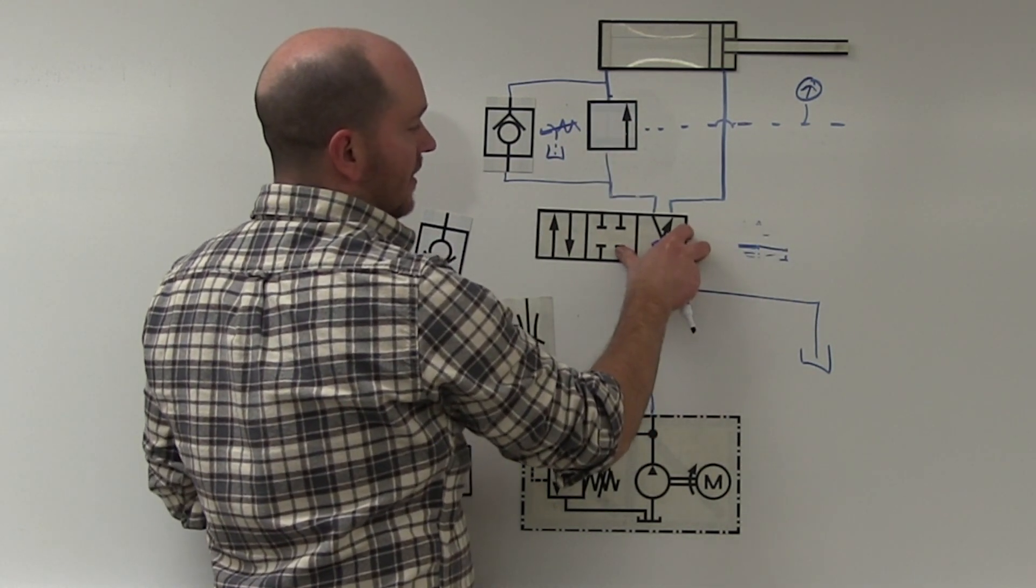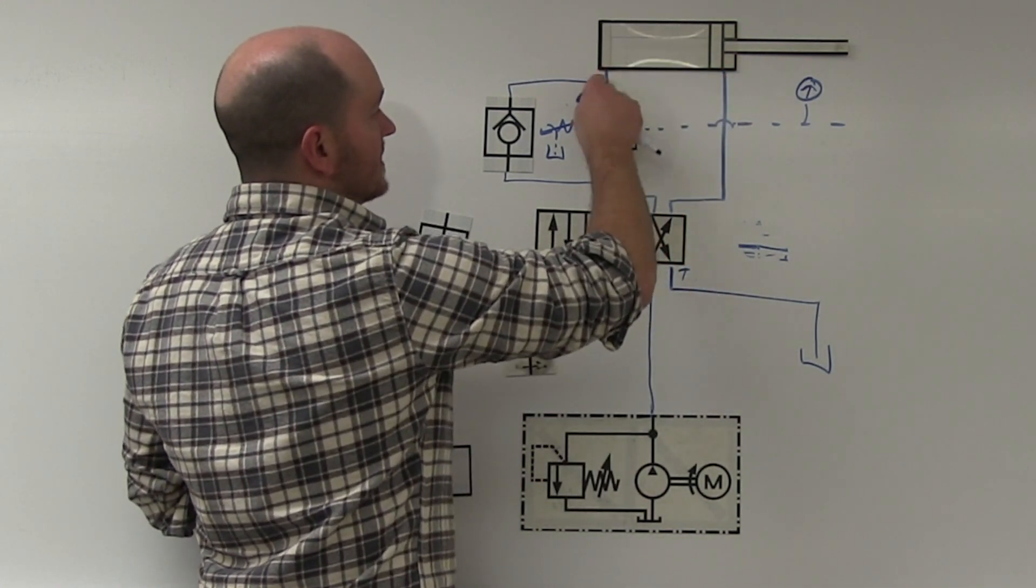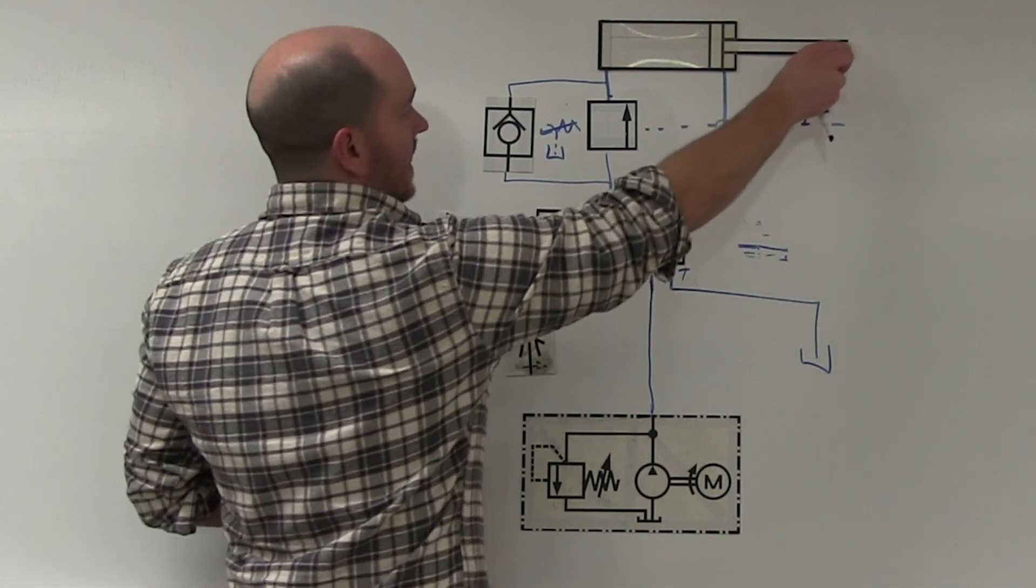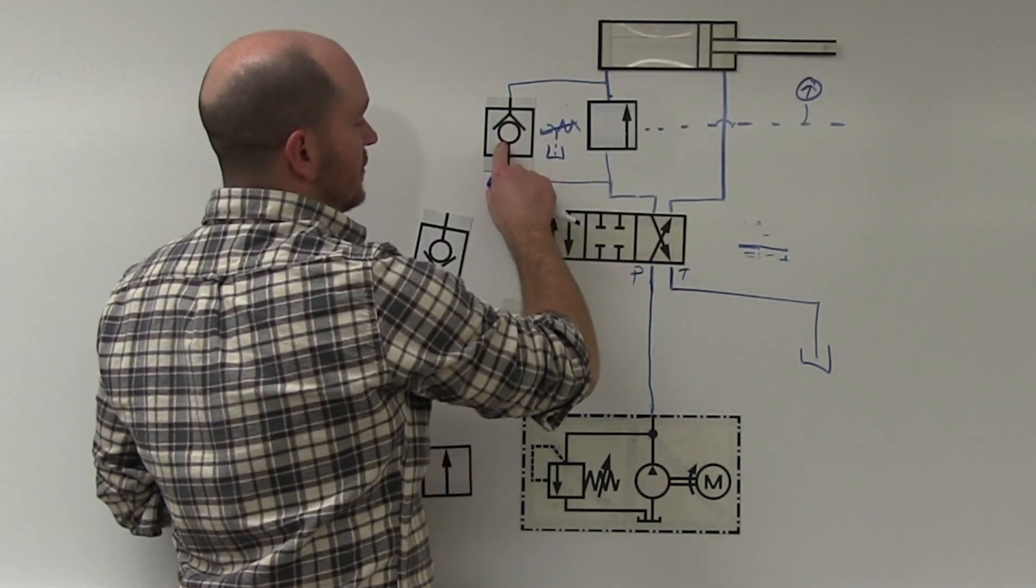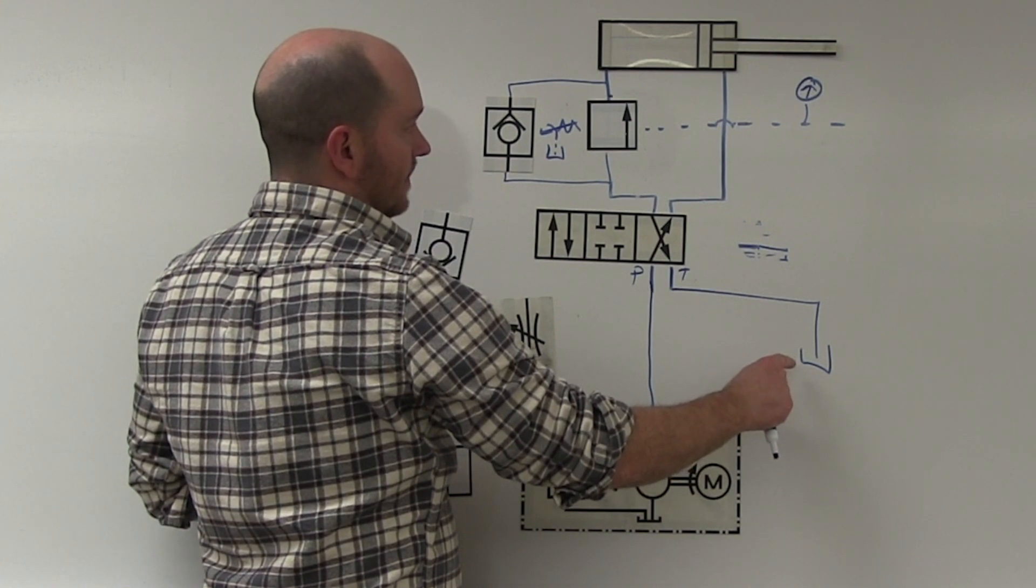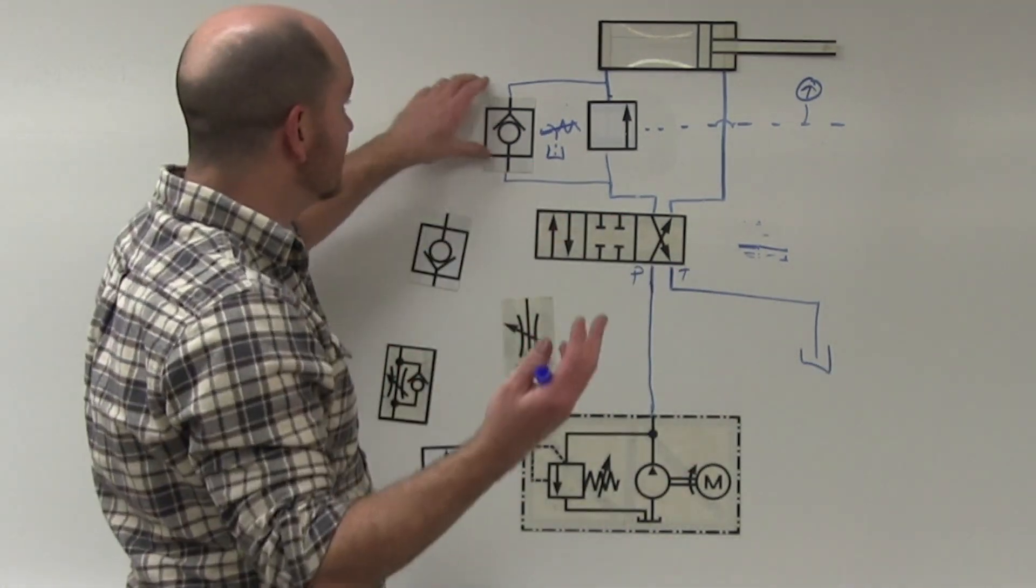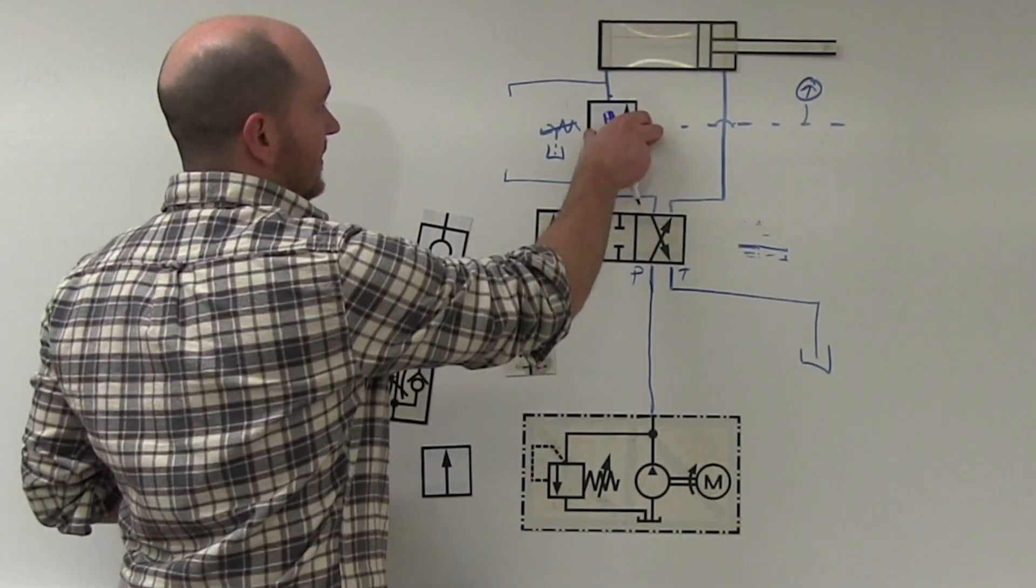The solenoid over here activates. Pressure comes up through here. This oil needs a path to exhaust back to tank. So as this goes, it goes through the bypass check valve, down to here, back down to tank. So in this case, we need that bypass check valve.